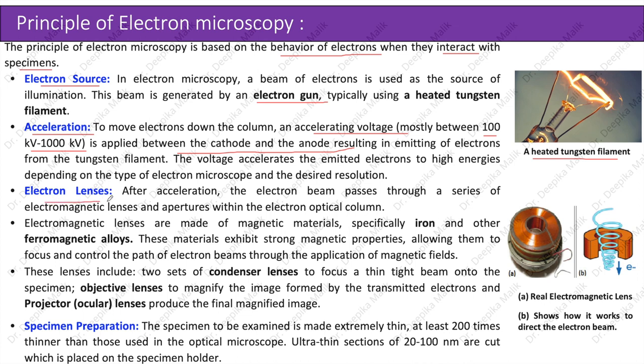Electron lenses: after acceleration, the electron beam passes through a series of electromagnetic lenses and apertures within the electron optical column. Electromagnetic lenses are made of magnetic materials, specifically iron and other ferromagnetic alloys. These materials exhibit strong magnetic properties, allowing them to focus and control the path of electron beams through the application of magnetic fields.